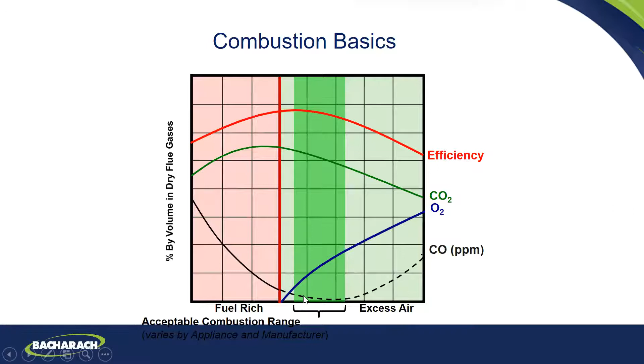We have recommendations in your boiler; your furnace manufacturer has recommendations on where you should be, okay? So let's say I put my analyzer on here. If you have an analyzer, you recognize something like this, regardless of whose you have. So this would be a boiler or furnace that's really out of spec. Your oxygen is really high. You shouldn't be running up here. So you have 10% oxygen. Your efficiency is low, at 78%. CO is low, but your stack temperature is high.